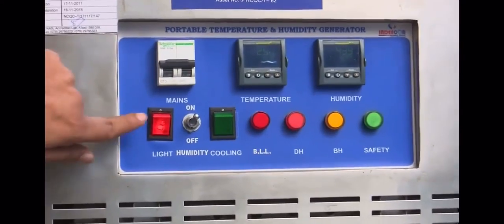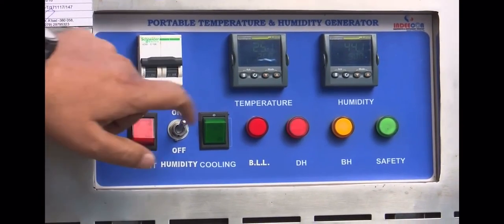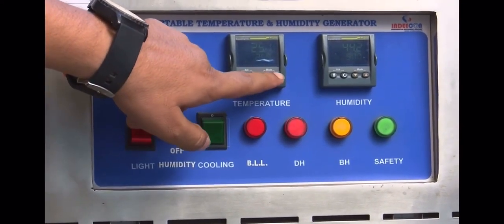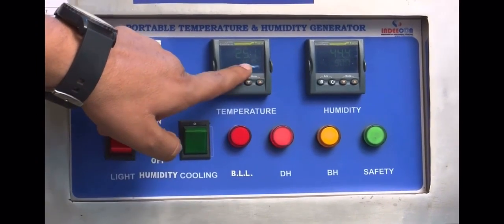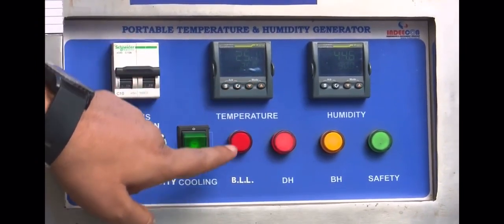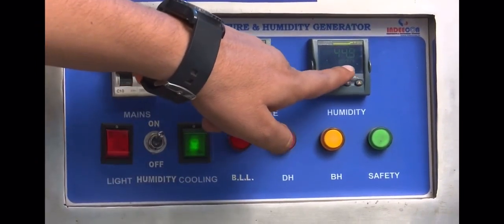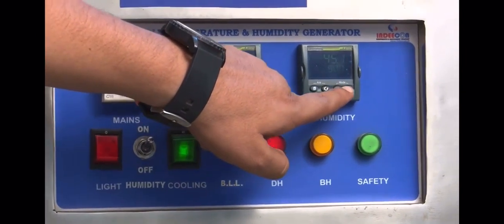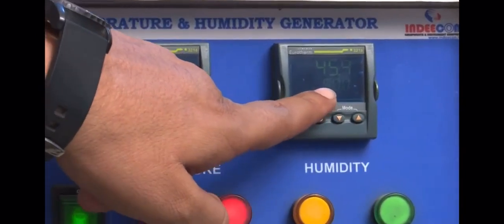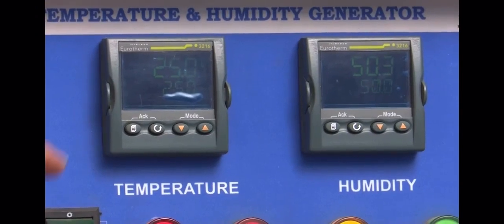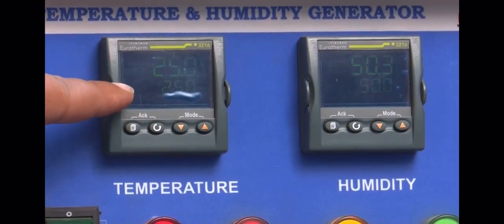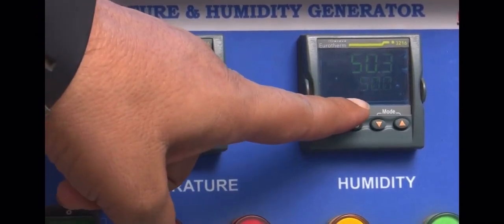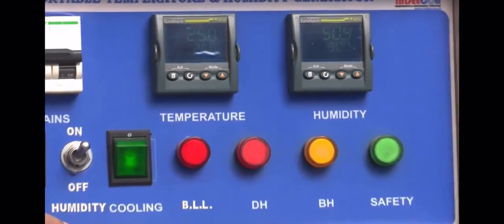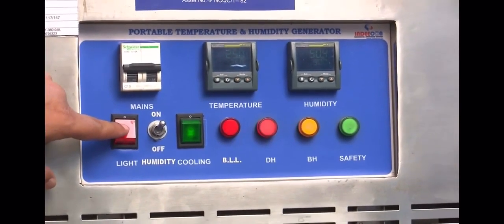For calibration of temperature and humidity, set the desired value of temperature 25 degrees centigrade and humidity 50% RH on the controller of the environment chamber. When the set temperature and humidity of 25 degrees centigrade and 50% RH is reached, allow the temperature to become stable for minimum 2 minutes.